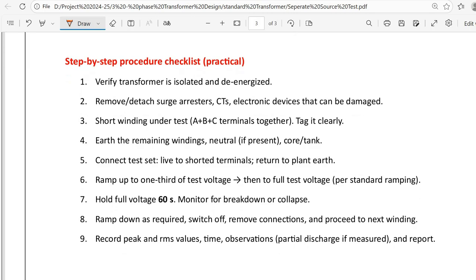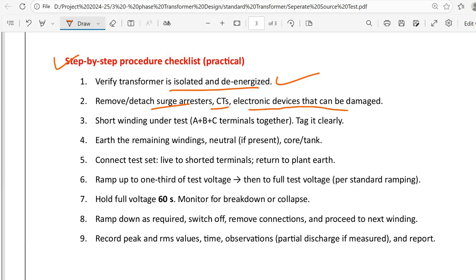So what is the step-by-step procedure checklist? Verify the transformer is isolated and de-energized. Remove and detach surge arrestor, CT and electronic devices that can be damaged. Short the winding under test, the ABC terminals, together and tag it clearly. Earth the remaining windings, the neutral if present, the core and the tank. Connect the test set live to the shorted terminals and the return path to earth.